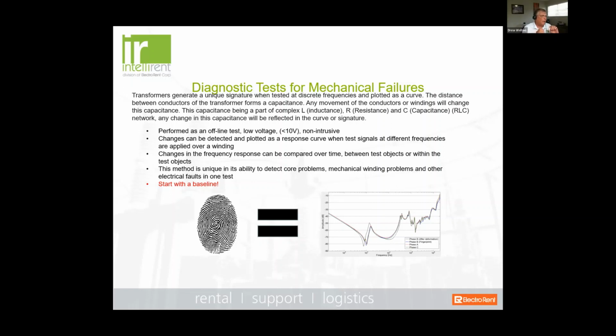And one of the important things is that we have to have a baseline of the frequency response. Okay, and it's important that if you're ordering a new transformer, you're specifying a new transformer with the OEM, make sure before it leaves the factory that you get a fingerprint of that SFRA and that test is performed and that record is available for you, because you'll want to check it again and run the exact same test once it gets ready for commissioning.